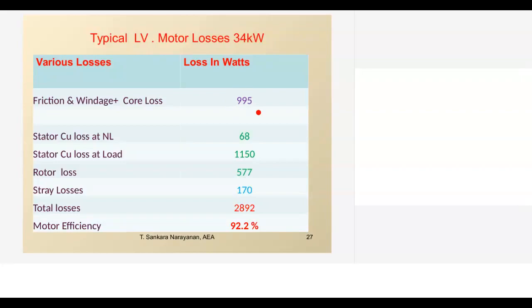Then the I square R loss, and if you see, the losses are increased in this. So what we tell is that the iron loss increase is there because while manufacturing, varnish is put on the motor, then it is dipped inside the varnish tank for 1.5 hours or 2 hours. When rewinding is done, such things do not happen. Normally, the rewinder will do varnishing by brush only. So predominantly the no load loss, the iron loss in the stator, will increase. Marginally, there will be an increase in the stator copper loss because the resistance increase will be less.